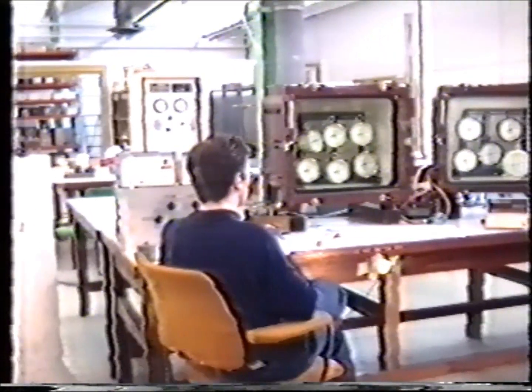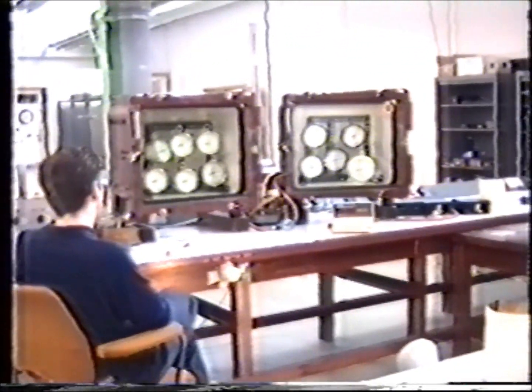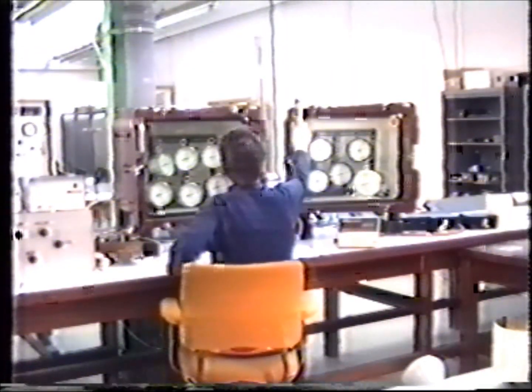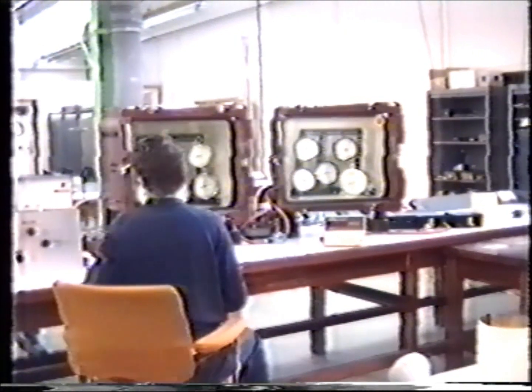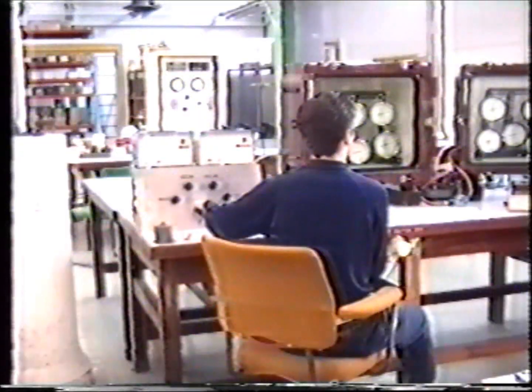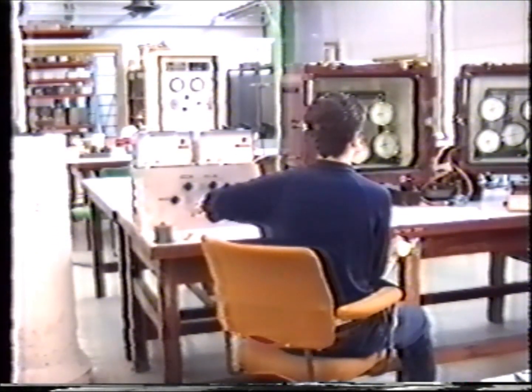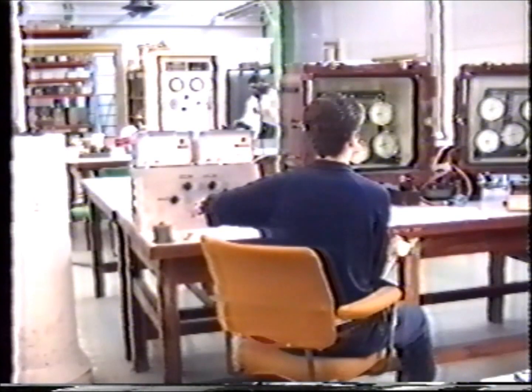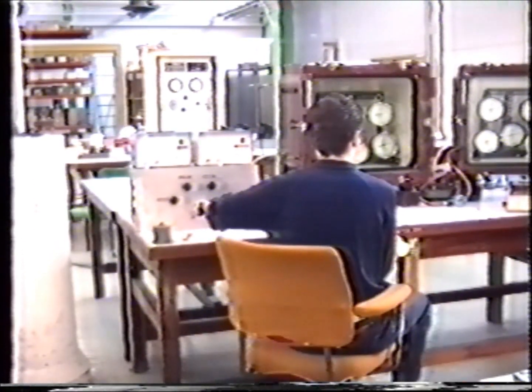Two pressure chambers are linked to pumps to provide a calibration facility for dial aneroid barometers, used extensively by the Royal Navy. Even these expensive items require the action of a rubber mallet to ensure a correct reading. An accurate digital barometer is used as a traceable standard, and pressure can be adjusted over the working range of 900 to 1050 hectopascals. Dial aneroid barometers often arrive from the Royal Navy in a smashed up state, obviously having fallen off the wall in a storm in the Bay of Bengal. You would have thought they'd use a bigger nail.